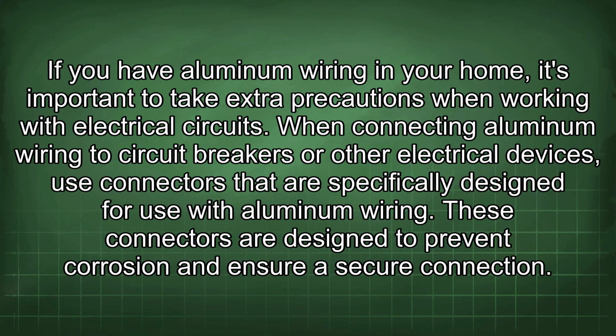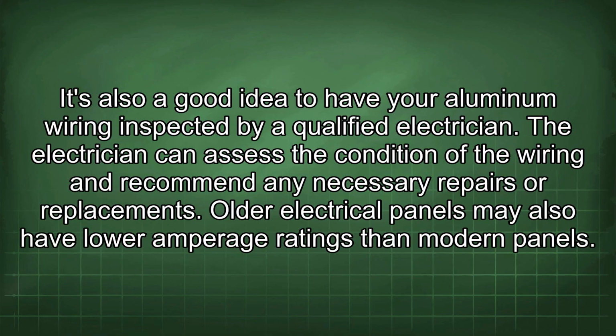When connecting aluminum wiring to circuit breakers or other electrical devices, use connectors that are specifically designed for use with aluminum wiring. These connectors are designed to prevent corrosion and ensure a secure connection. It's also a good idea to have your aluminum wiring inspected by a qualified electrician. The electrician can assess the condition of the wiring and recommend any necessary repairs or replacements.